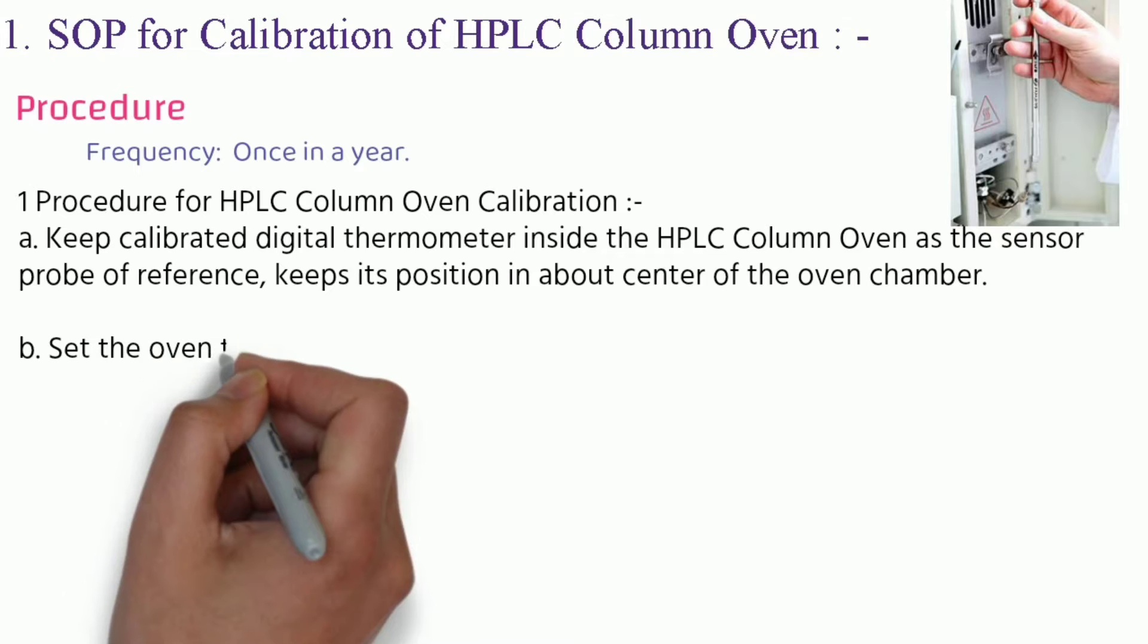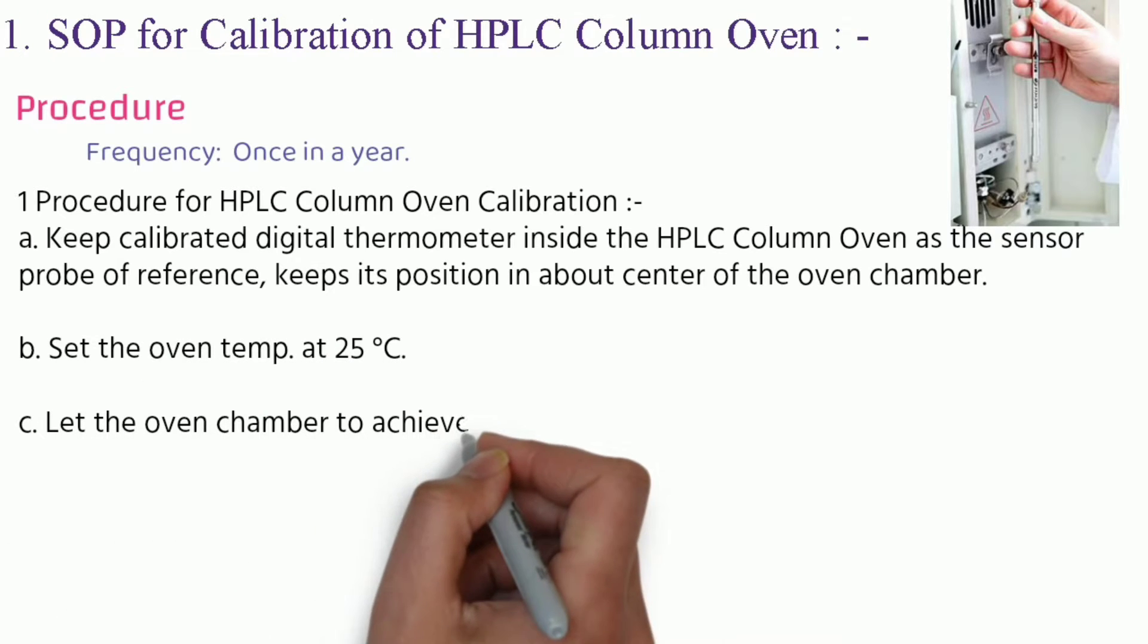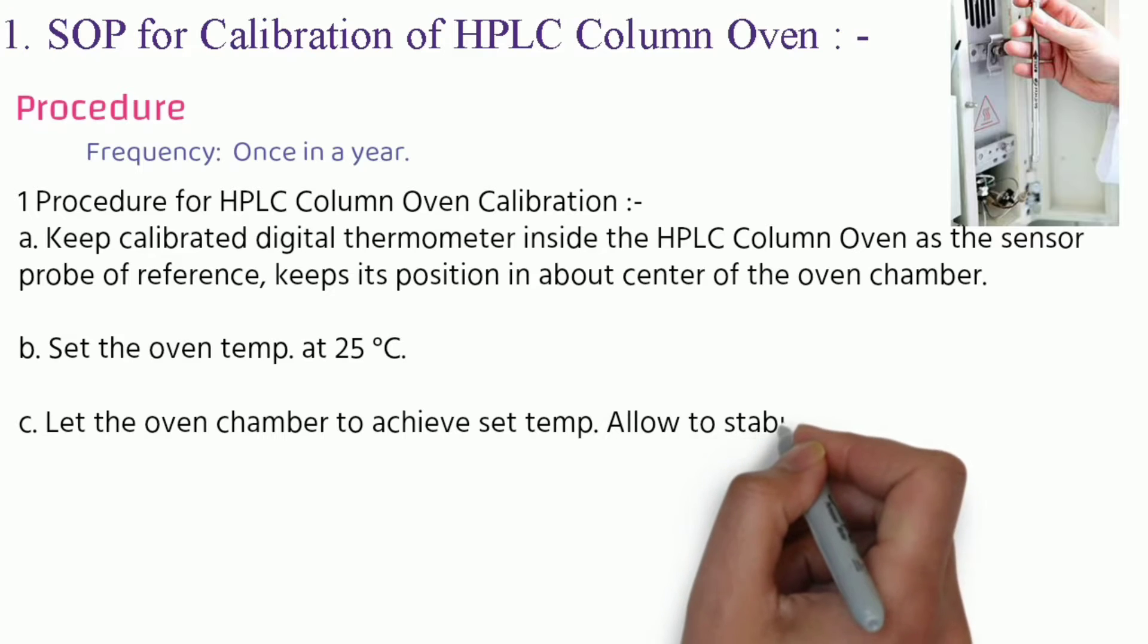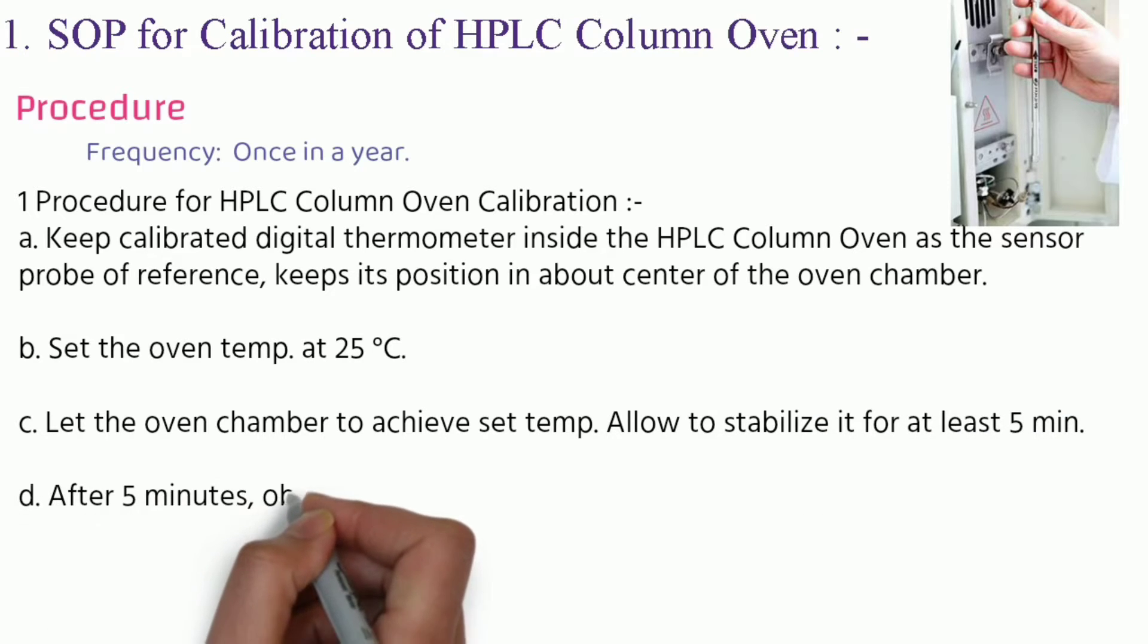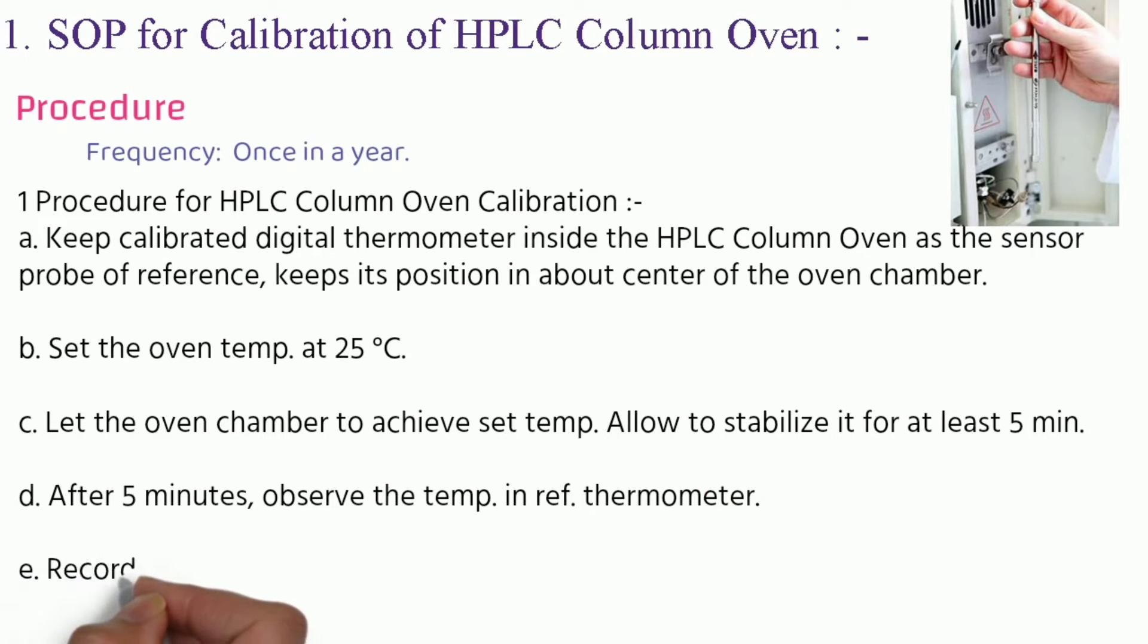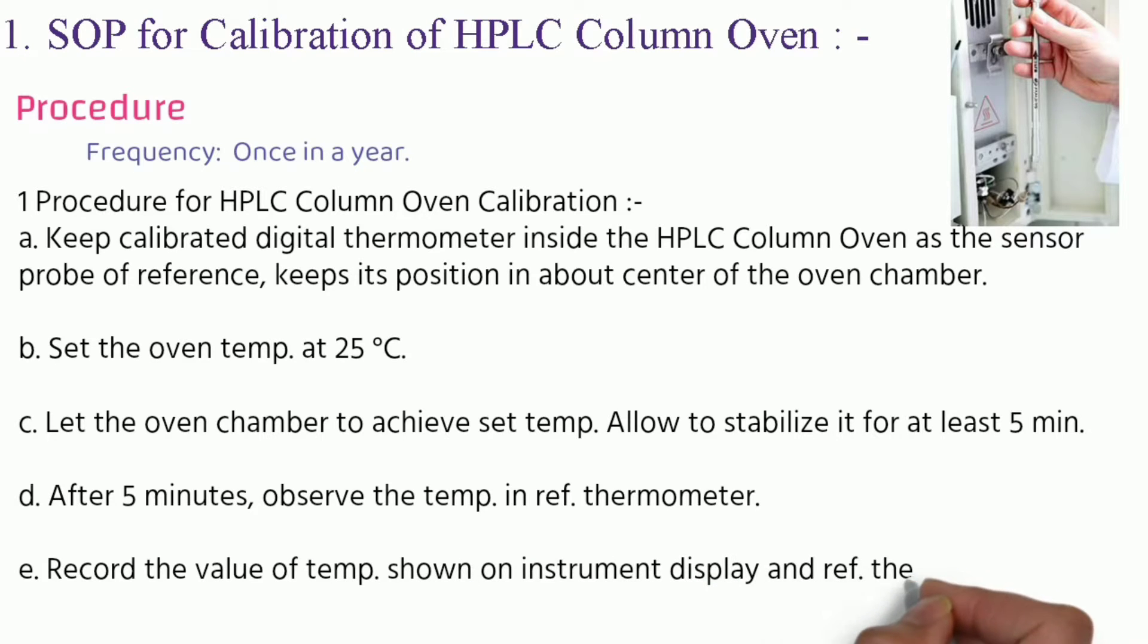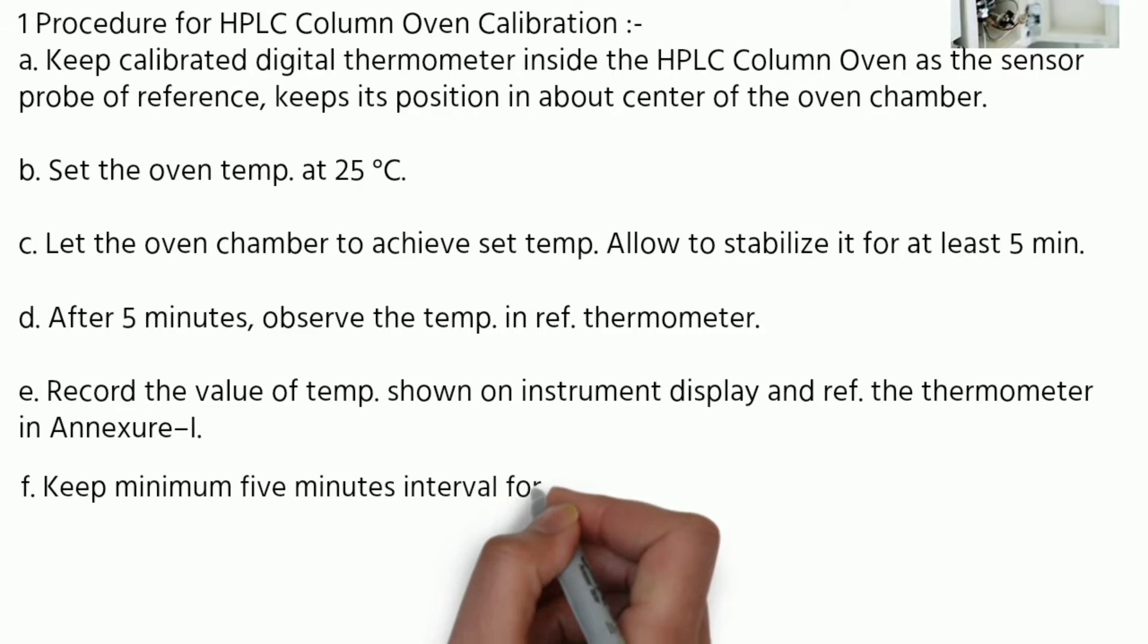Set the oven temperature at 25 degrees Celsius. Let the oven chamber achieve the set temperature. Allow to stabilize it for at least five minutes. After five minutes, observe the temperature in reference thermometer. Record the value of temperature shown on instrument display and reference thermometer in annexure 1. Keep the minimum five minute interval for first and second readings.